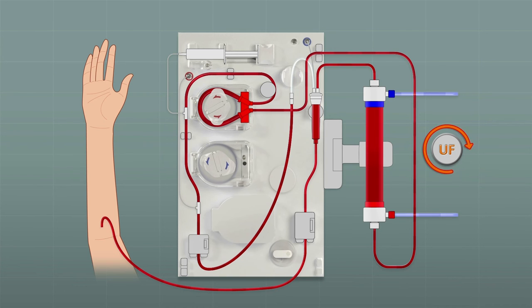Again the UF pump is responsible for delivering the reinfusion volume. Half of this volume will be moved out of the dialyzer outflow and return the blood to the venous chamber. The other half will be moved from the dialyzer inflow to the venous chamber by the blood pump, now turning in the reverse direction. From the venous chamber, the blood is returned to the patient.